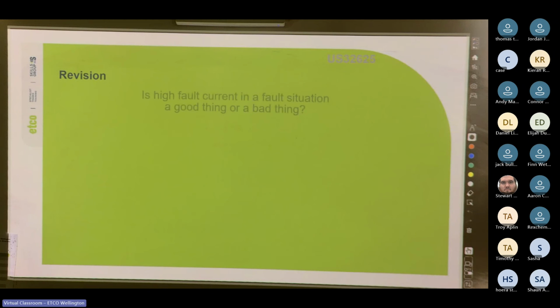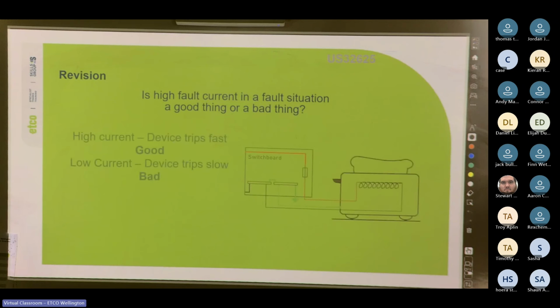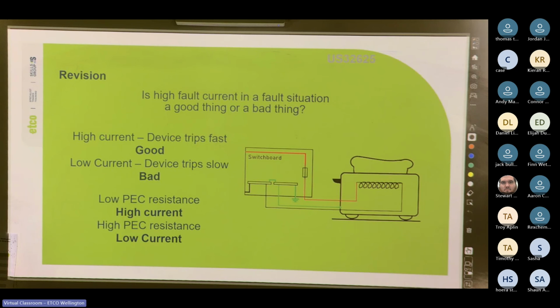Cool. So here's a toaster with a solid earth. The breaker trips instantly. With a poor earth, the toaster still works, but the casing is live. It is deadly. It's the same logic that applies in damp areas, except water makes things far greater. So low PEC resistance, high current. High PEC resistance, low current. Cool. So that's revision out of the way.